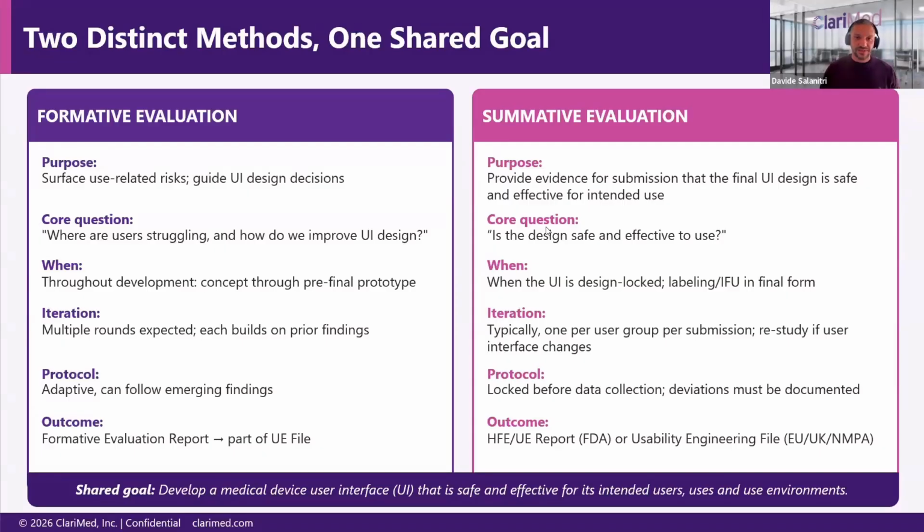Having a general guideline of how to design a summative just from the submission pathway is difficult, because it really depends what your device is, what risks there are, how many critical tasks, any information you have beforehand, and whether there are any relatable devices.